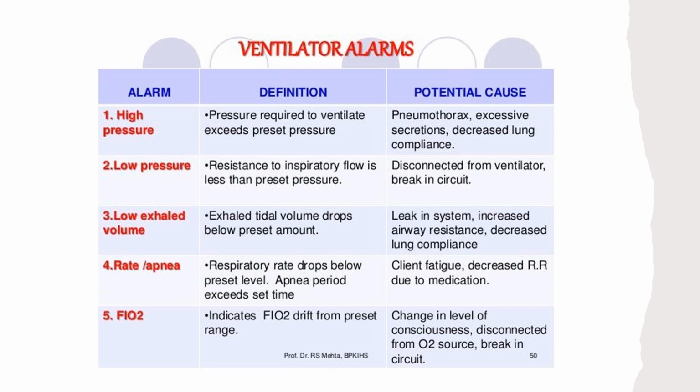And then there's a low exhaled volume. Exhaled tidal volume drops below the preset amount. So this could be if there's a leak in the system, any increase in airway resistance, or a decrease in lung compliance. There's an apnea alarm. So we may see this a lot on patients who are on spontaneous breathing trials. Their respiratory rate drops below a preset level, and they have a period of apnea, and that's going to alarm.